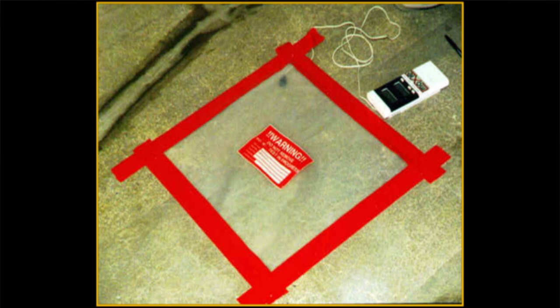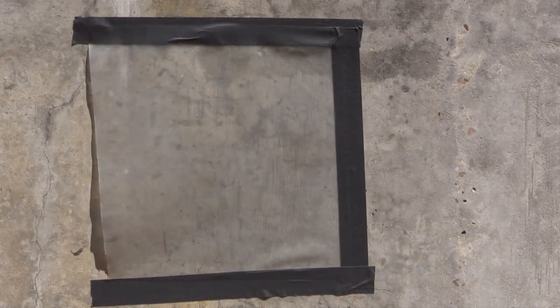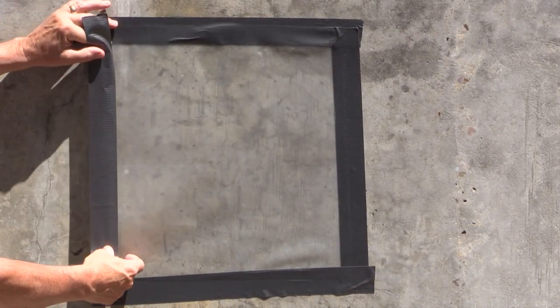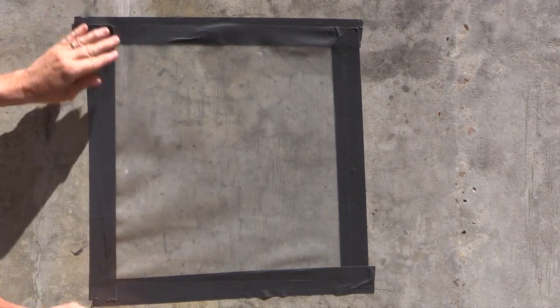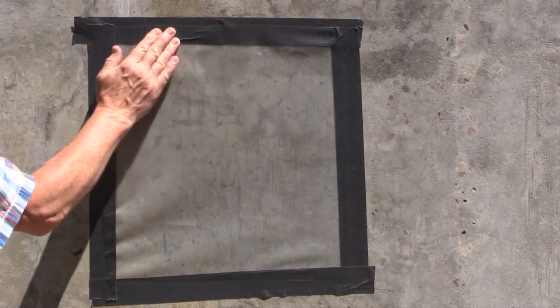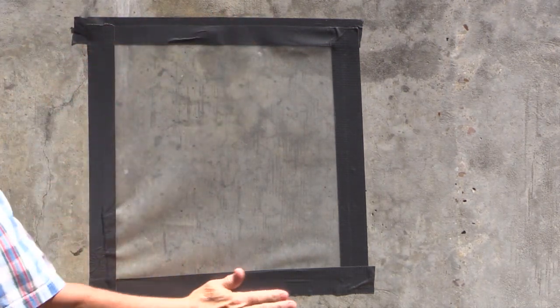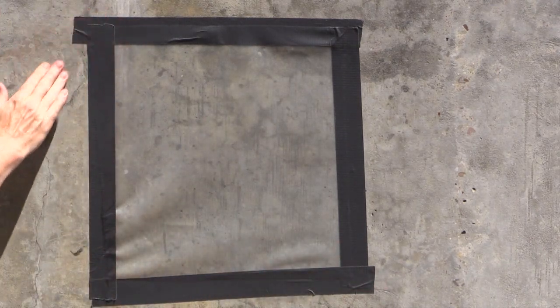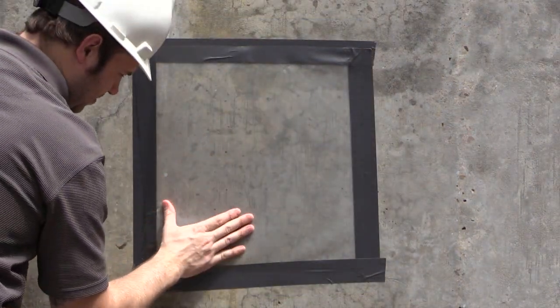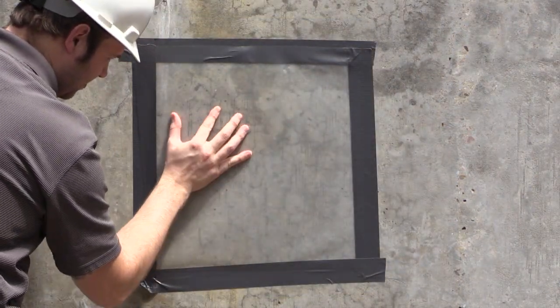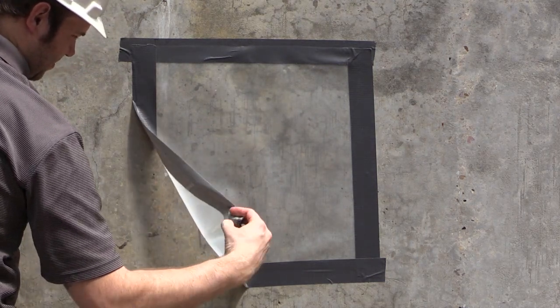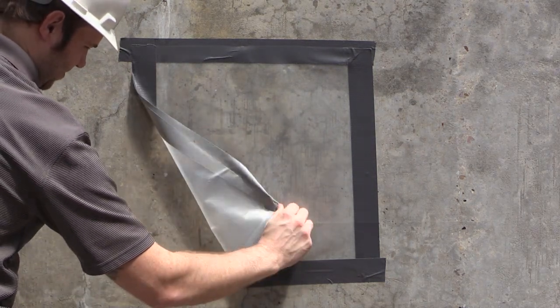The plastic sheet test is addressed in ASTM D-4263. Although the standard was developed for coating system preparation, it is also used in the flooring industry. This is a non-destructive test that requires firmly taping the perimeter of a sheet of plastic, about 18 inches by 18 inches in size, to the floor or wall and allowing it to remain in place for a minimum of 16 hours. At the end of the exposure period, the underside of the sheet and the surface of the concrete are visually examined for the presence of moisture.